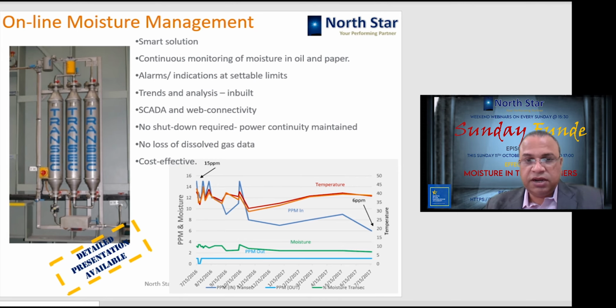Here you can see it was 15 ppm in the beginning, and when this system was put into use, then it came to 6 ppm in a period of 1 year. So 50% moisture got eliminated from the transformer, and it has not got added again. Okay, so these kinds of graphs are available.